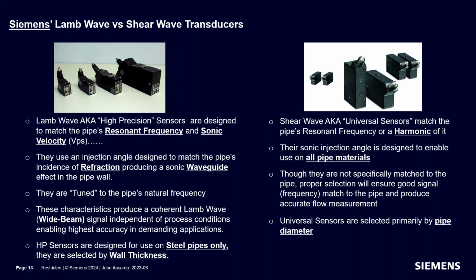One of the things that sets us apart from other manufacturers is this fact that we tune our transducers to the pipes by doing these frequency sweeps. Other manufacturers tout that they have Lamb wave transducers as well, but none of them do the frequency sweep. They operate at fixed frequencies. So even though you have a Lamb wave transducer, it doesn't mean you're going to get the ideal waveform on the pipe if you're not matching the resonance of the pipe. And it's very easy to demonstrate how most of the time you're not operating at the primary frequency of the transducer. You're operating at what the pipe likes, and it doesn't necessarily match up with that transducer's primary frequency. It's a primary harmonic of the frequency. But if you stick with just the transducer frequency, chances are you're not going to pick the best frequency for the pipe that you're on.